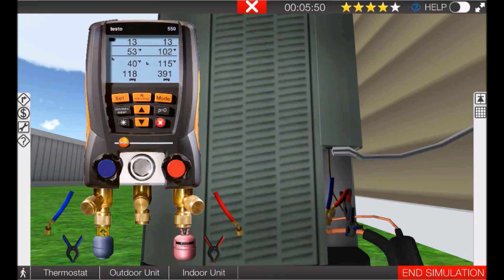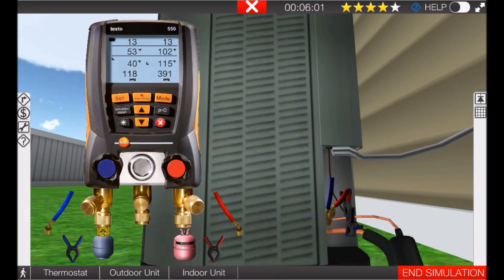Then we will overcharge it and look at what happens to the system pressures. Then we'll undercharge it and look at the system pressures. The first thing you should do when you arrive at a call that has inadequate cooling is check that filter and make sure that the coil and the filter are clean before you throw your gauges on the system. Alright, so we'll see you on the next video.